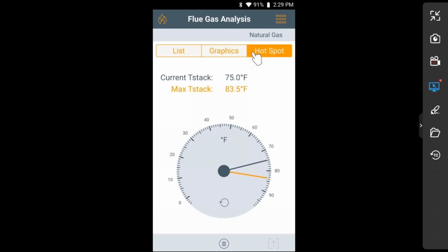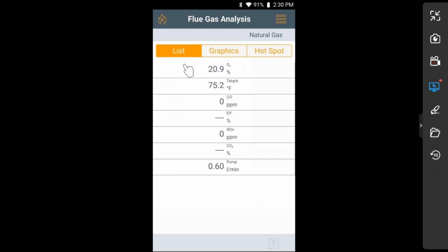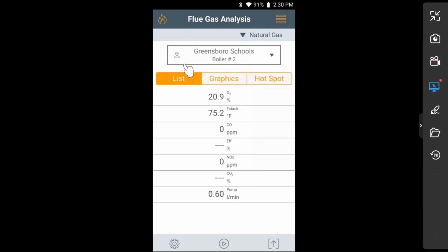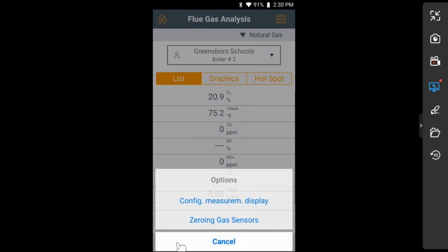I just breathed into the probe to bring the temperature up a little bit, and now it would read around 350 degrees or so, but you would get an idea of where to put your probe in the stack where it's the highest stack temperature. We don't use it as much here in the United States, but it is a good indication of where to take an efficiency test when you're looking at the highest stack temperature in the stack. The gear on the bottom, when I press that, what I can do with the analyzer is configure this measurement display that you see here.